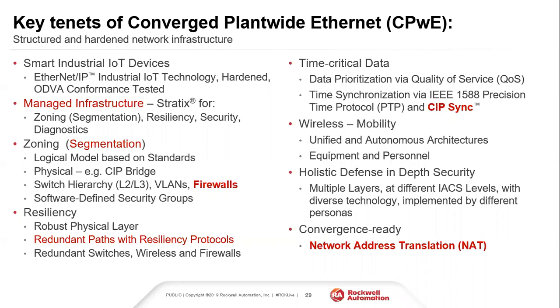So we didn't really talk about firewalls, but just know that in most cases, firewalls are put on the network to not necessarily segment a piece of traffic, but essentially put a wall around it and force it so that you're only communicating one way or another on specific things that you guys are comfortable with. So think of EtherNet/IP on the Rockwell side or Modbus communication. You can ignore everything else and just open up that one specific option that allows you to do Modbus communication or EtherNet/IP communication. And you put a wall and a border around everything else. So if you guys have any security questions or anything like that, it's one of the things that I focus on.